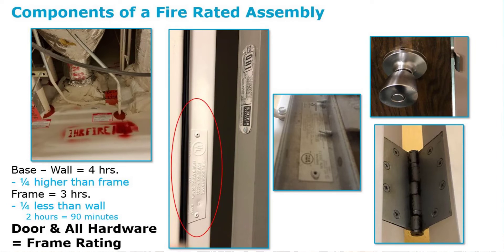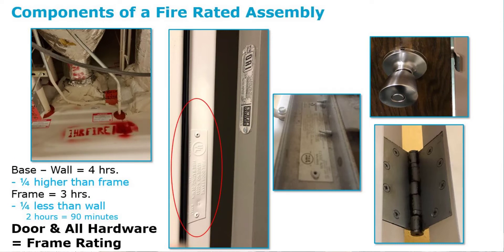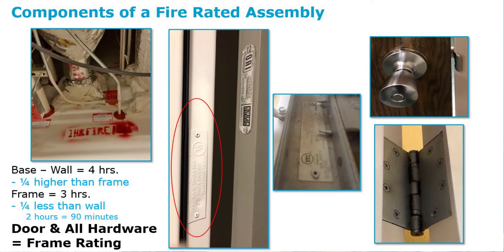Let's go back to the wall and start there. The wall is the base of every fire rated assembly and will often be rated for four hours or two hours. If I have a four-hour rated wall, the frame is going to be rated a quarter less — so a three-hour rated frame. From there, everything else is rated to match the frame: a three-hour rated door, three-hour rated hardware, including the locks, hinges, and closers. Everything else will match the frame.